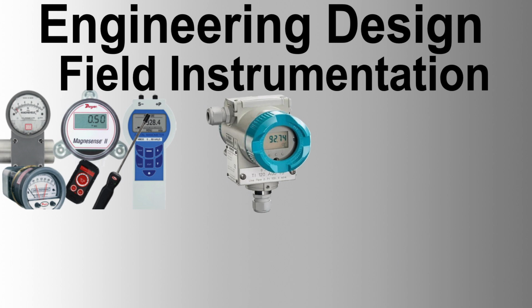Hydrostatic testing. Hydrostatic testing must be performed on all pressure-containing parts to ensure their integrity and compliance with the specified requirements. The test pressure must be 1.5 times the design pressure and held for a minimum of 30 minutes. Any leakage or pressure drop during the test must be investigated and rectified before retesting. Test certificates must be provided to the purchaser for review and approval.